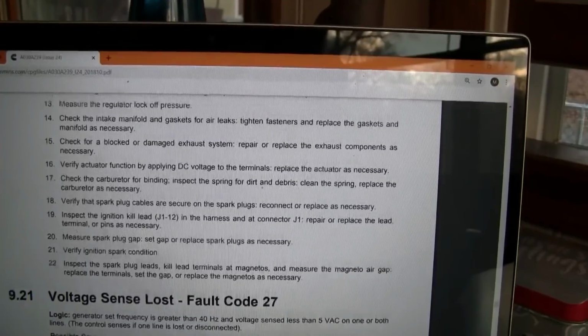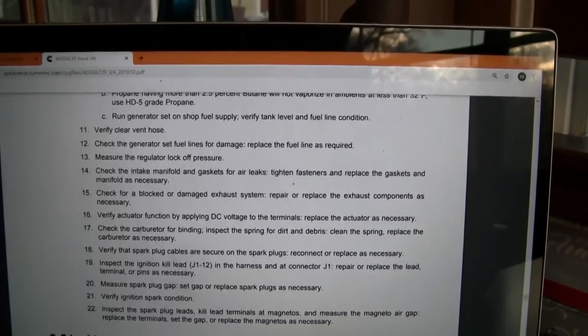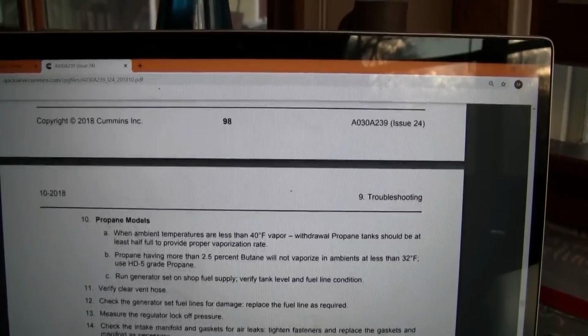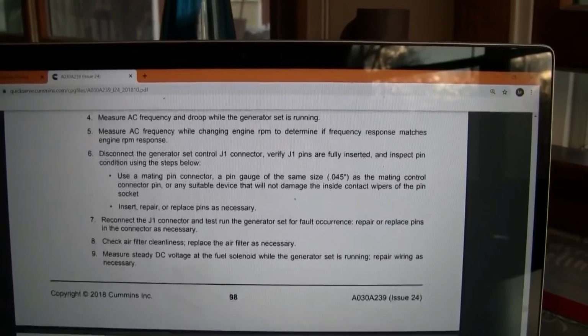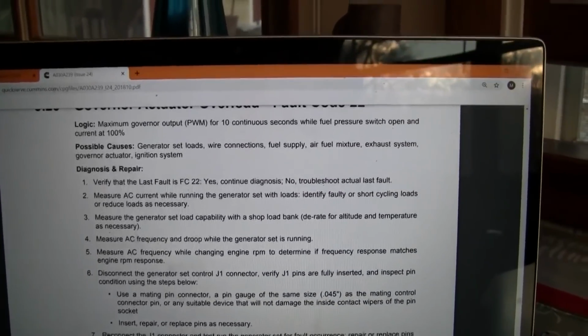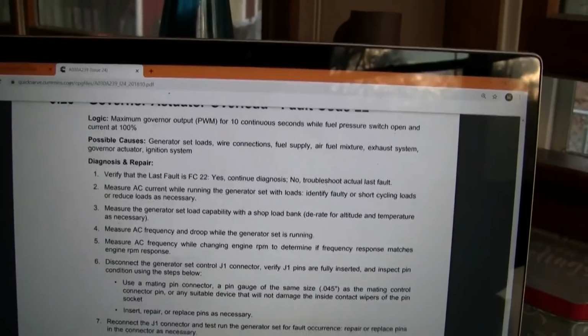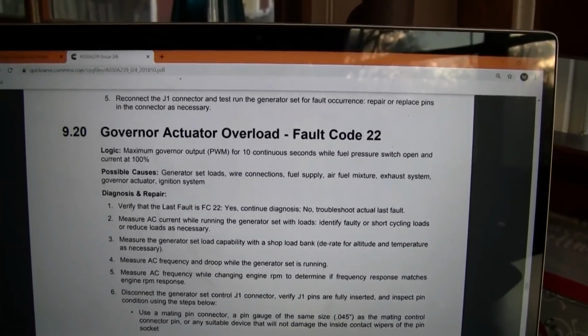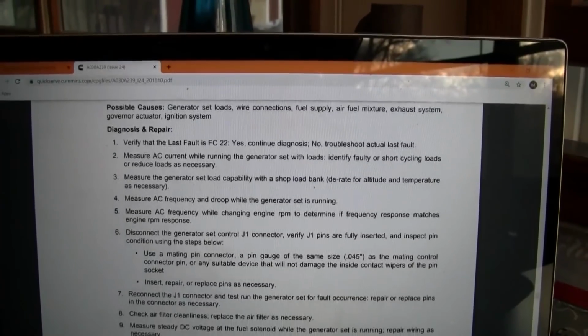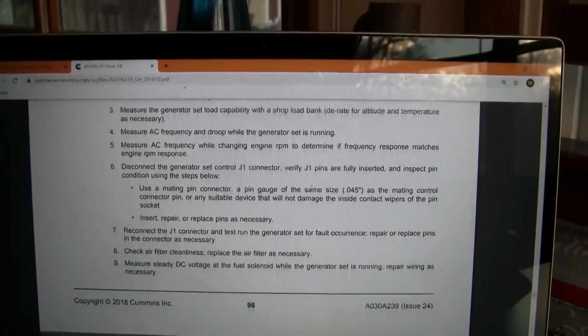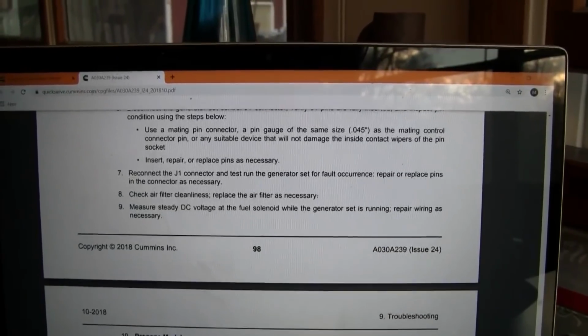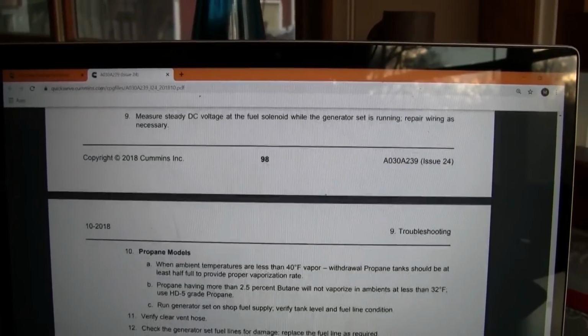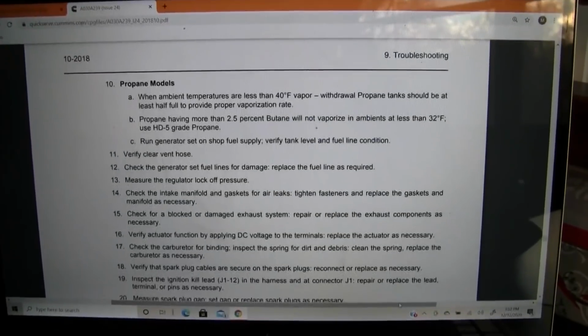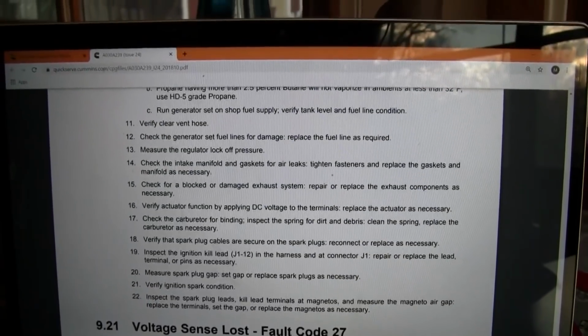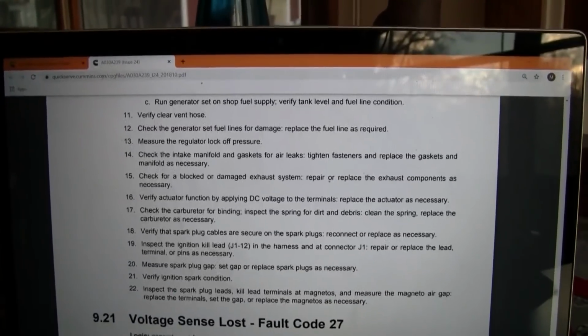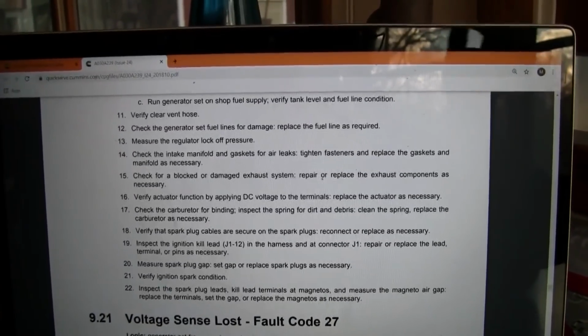So it could be a few different things, of course. It seems to be an engine performance issue, which I think is my fuel supply, because I'm riding the ragged edge of the 4 to 7 inch fuel supply pressure. I'm pretty much right at 4 inches, 4.5 inches of water column, so I could tear into the engine, check for vacuum leaks, do some things like that, readjust the valves, but I don't think that'll gain me anything. I really like to have these units run right at their maximum fuel supply inlet.